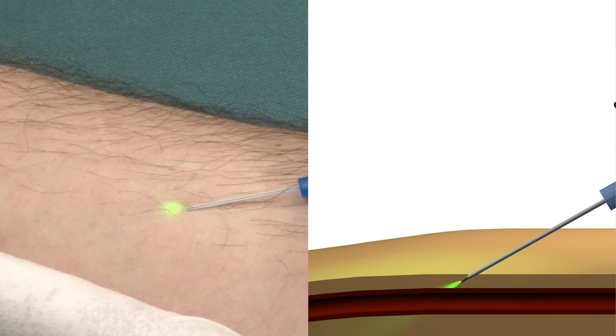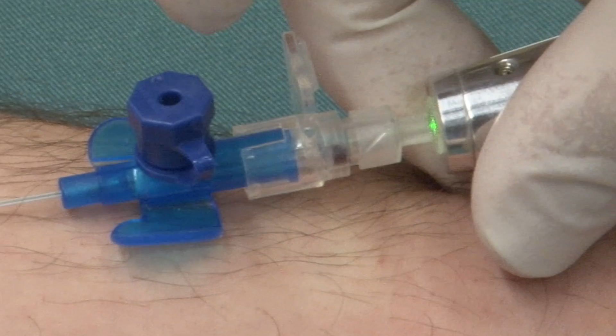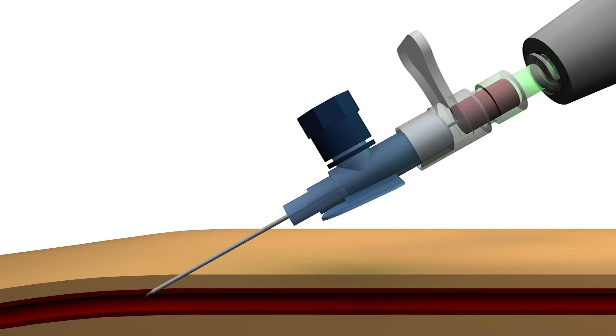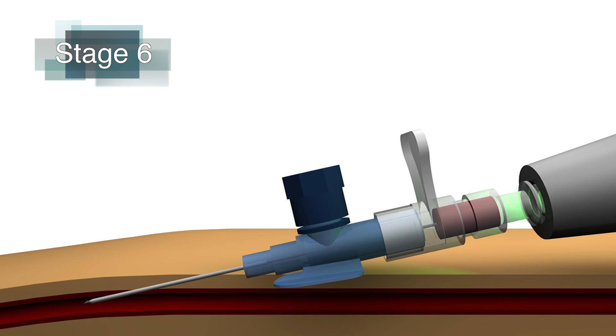Stop advancement of the catheter and observe the first flashback of blood in the clear flashback chamber, needle flash, which confirms that the needle tip is in the vein. Lower the catheter to be almost parallel to the skin. Advance the entire catheter and needle as a unit slightly to ensure that the catheter tip is in the vessel. Advance the catheter off the needle slightly. Observe a second flashback of blood, catheter flash, between the needle and the catheter to confirm that the catheter is successfully in the vessel.